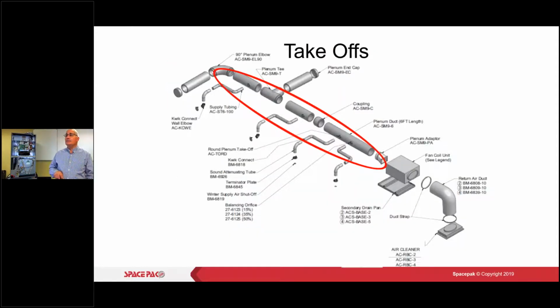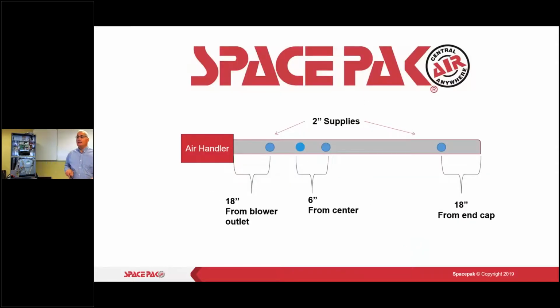Now our takeoffs, again, 6 inches on center, no closer. And also try not to have, if this is my plenum run here, my takeoffs coming up from the top and then bending over and coming out. Take them out to the side. We don't want all these bends. Adding extra length that you don't need is just going to cut down on the CFM. So again, that's what we want to do: 18 inches off of the blower before my first outlet, 6 inches on center, 18 inches away from the end cap. Can't stress that enough.